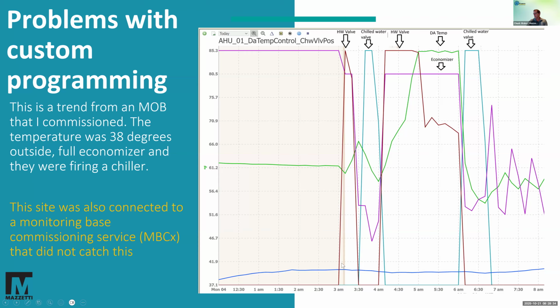It starts up at 3 o'clock in the morning because it's 37 degrees outside. It opens up its hot water valve, which is kind of expected, but the economizer was also fully open. Half an hour later, it drops that and turns on the chilled water valve, which, by the way, starts the chiller. Then it changes its mind and says, no, I don't really need that, I need the hot water valve instead. But then it opens the economizer again. For those of you that don't know, the economizer is your outside air dampers.